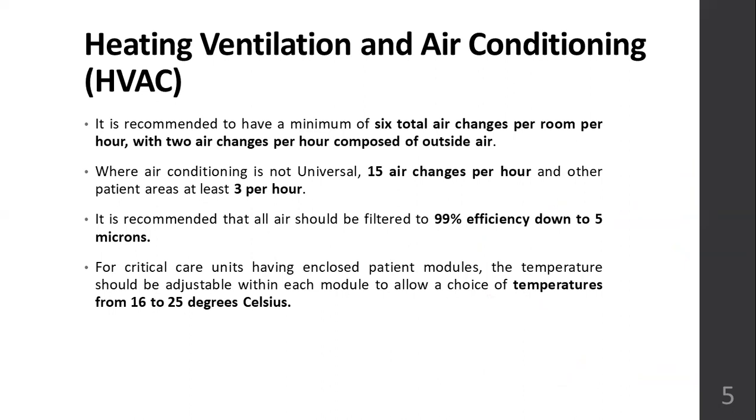Next, you have heating, ventilation, and air conditioning. HVAC stands for heating, ventilation, and air conditioning. It is recommended to have a minimum of 6 total air changes per room per hour, with 2 air changes per hour composed of outside air. What are these air changes?